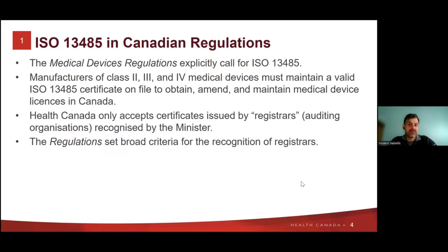In terms of the integration of 13485, the regulations explicitly call for ISO 13485. And so it's not a reference to good manufacturing practices or some other sub-regulations, as some countries have internalized the requirements of 13485 into a national regulatory document. We've not gone this route. We've simply said, there's a standard 13485, you must apply it. And so what the regulations say is that the manufacturer has to supply a quality management system certificate to ISO 13485 to obtain a medical device license, to amend it, so to bring in changes, and also to maintain it. So they have to be renewed on an annual basis. And so the manufacturer initially has to provide that 13485 certificate and make sure that it remains valid, so that if it expires, it is replaced with a renewed certificate on file.